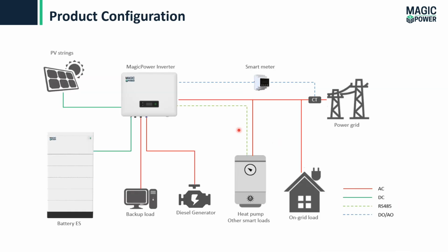Next is system configuration. Again, the basic components for the system are PV, battery energy storage system, hybrid inverter, and some backup load and power grid. Basically, this system can connect to a smart generator, which can sense the signal if the system sends the signal to the generator, and some other smart loads like heat pump, and the on-grid load, which is directly connected to the power grid.